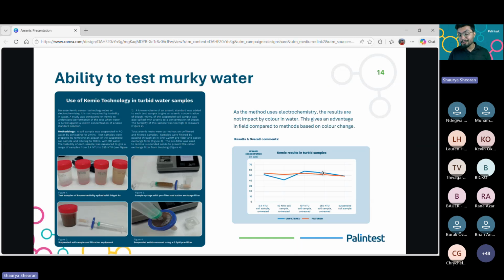Another unique advantage we talked about is the ability to test in murky water. As you can see on the left, we took different samples, and from the ground, it sometimes also has soil, especially when the water sample is coming from a borewell or a hand pump. But Kemio has the ability to also test the murky sample because it works on electrochemistry. It's not measuring color change, it's measuring the electric current, and that's why it's able to perform well even across turbid samples, which is really crucial in this type of application.